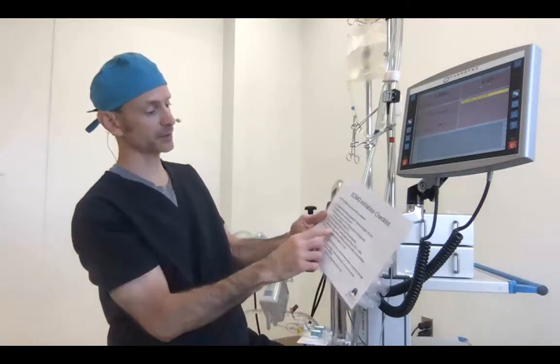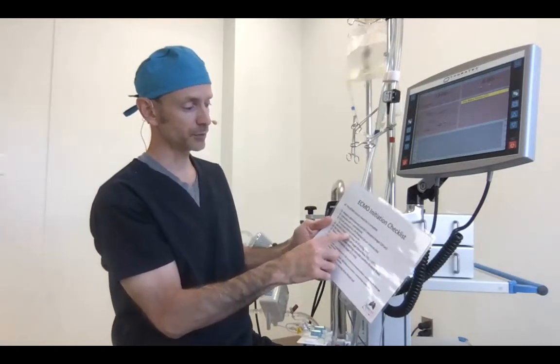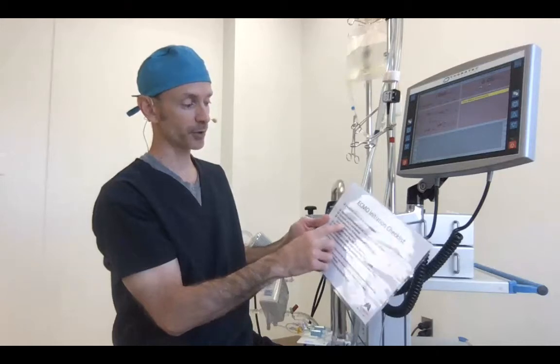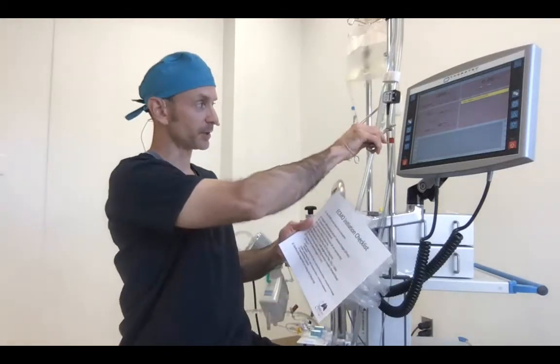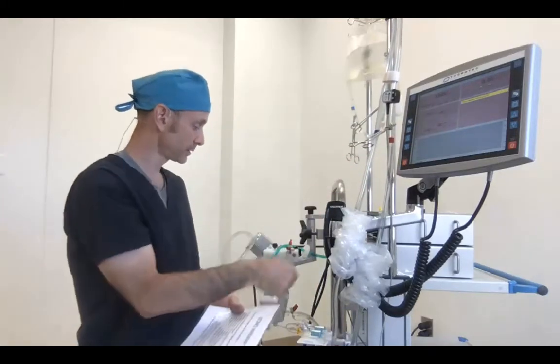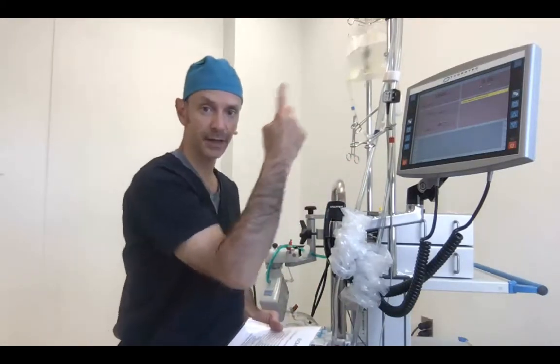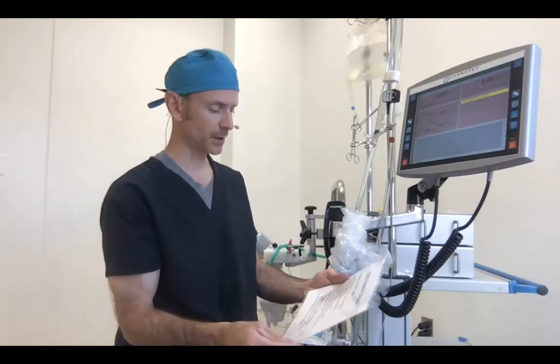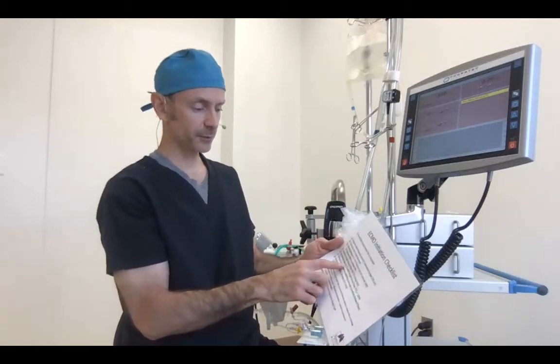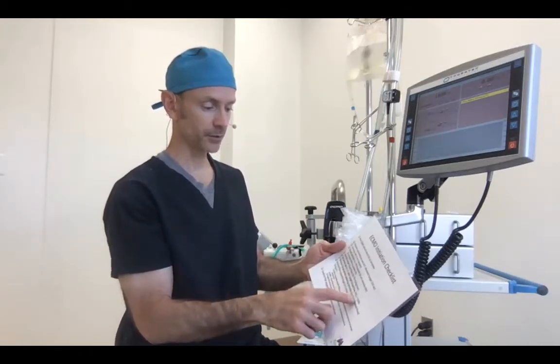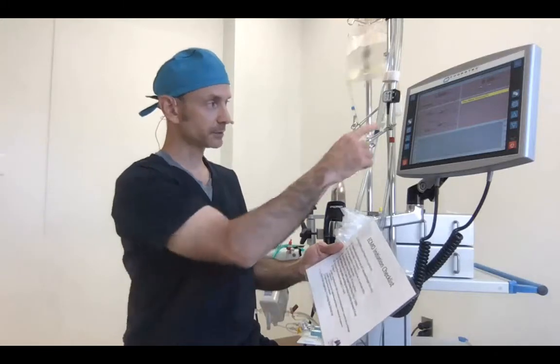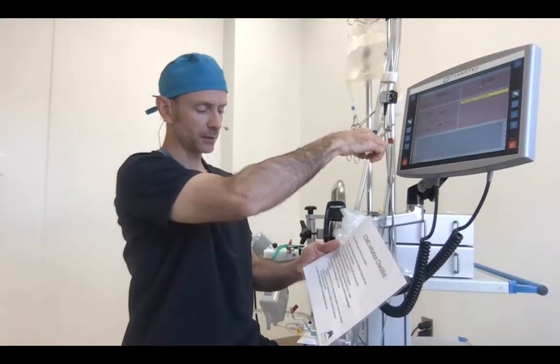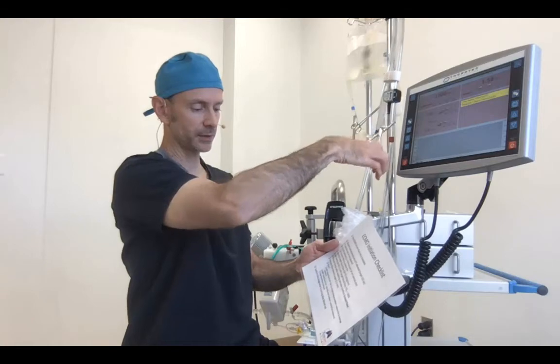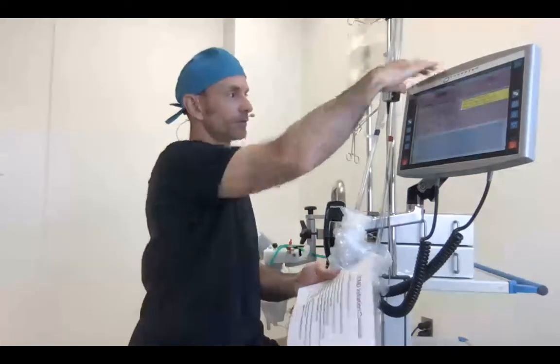So here we are on that checklist, and it says increase the RPMs to achieve a situation where your circuit pressure is greater than the patient's pressure. And that's what that means. Place your clamp, make sure you're measuring your pressure, compare that to what you see on the patient's hemodynamic monitor, either their CVP or their arterial blood pressure. Set your sweep gas rate to 1:1 with your targeted blood flow. Remove the clamps, and then, while watching the cannulas, confirm forward flow.